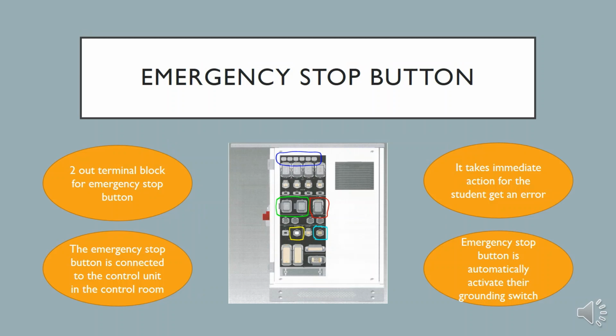For the side view of the Kit FC cabinet, there are two out terminal blocks for the emergency stop button in the green circle. The emergency stop button is connected to the control unit in the control room to ensure the safety requirement. It takes immediate action when a student gets an error while doing an experiment. Thus, the emergency stop button automatically activates the grounding switch when there is an error on the instrument.